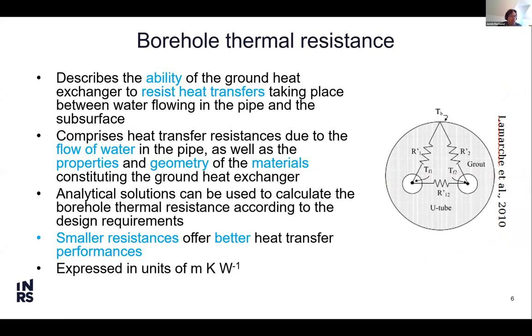Actually, we try to minimize borehole thermal resistance. The borehole thermal resistance, actually, it's a term that describes the ability of ground heat exchangers to resist heat transfer. Heat transfer that takes place, okay, this is a slice of a borehole, and this is my U-pipe in which the fluid circulates, and that would be the ground outside my borehole. So it's the resistance between the fluid and the borehole wall. So it comprises resistance due to flow of water in the pipe that we want to be turbulent to maximize heat transfer, as well as the property and the geometry of the material.